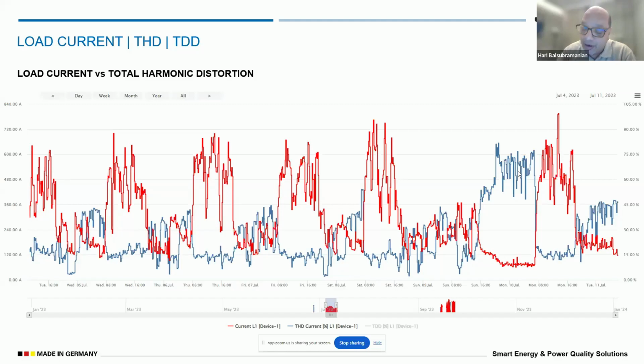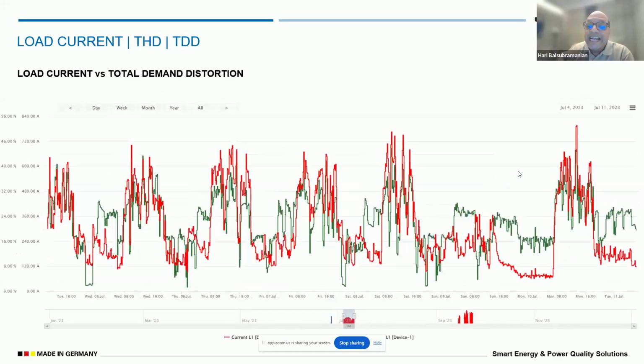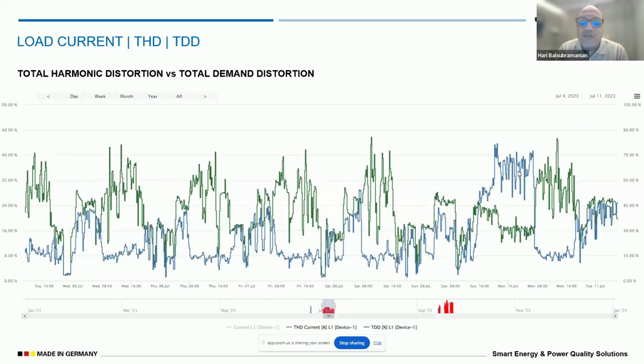We may have to take the parameter called TDD. TDD varies along with your loads most of the time. So if your load is high, then the TDD also goes high, and if the load is low, TDD also goes low. In this kind of phenomenon, now I will try to compare THD and TDD. For what will you do the compensation, for the total harmonic distortion or the total demand distortion? This is a question I put forth for us to think about. Maybe we can discuss it over a period of time or by the end of the session.